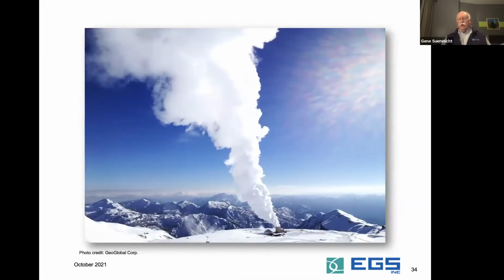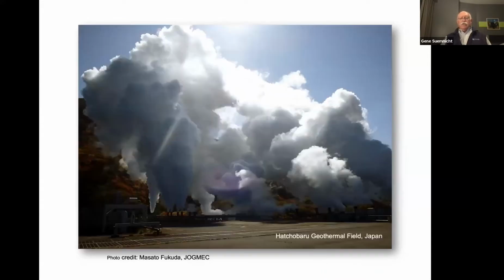We have a well, but that's not sufficient, because you need a number of wells to be able to take those volumes of steam and pipe it to a power plant. So an individual productive well could potentially generate maybe 5 to 7 megawatts worth of electricity. And a megawatt, for general background, for developed societies, is a sufficient amount of energy to satisfy the electrical needs of about 1,000 people.